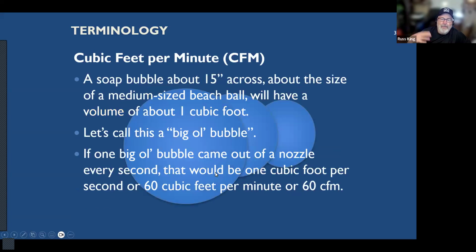And so I've come up with this example here. A cubic foot, it's hard to imagine cubes coming out of a register like that. It's easier to imagine circular bubbles. You've blown bubbles when you blow like that, and all these little bubbles come out. Imagine the same sort of thing happening at a register. Well, a cubic foot would be a bubble that's about 15 inches in diameter, a little bigger than a basketball, about the size of a beach ball. That would be a cubic foot. So we'll just call that a big old bubble. This big old bubble of air is coming out.